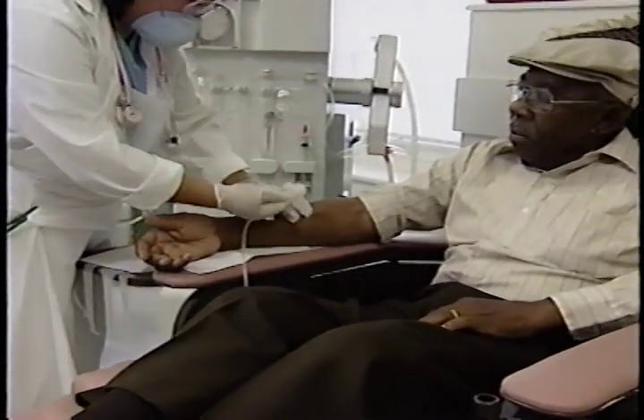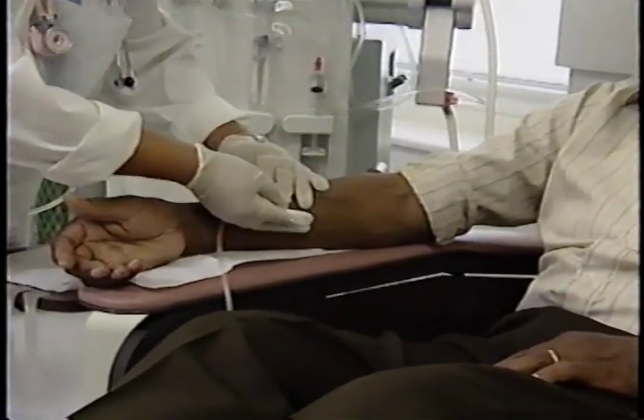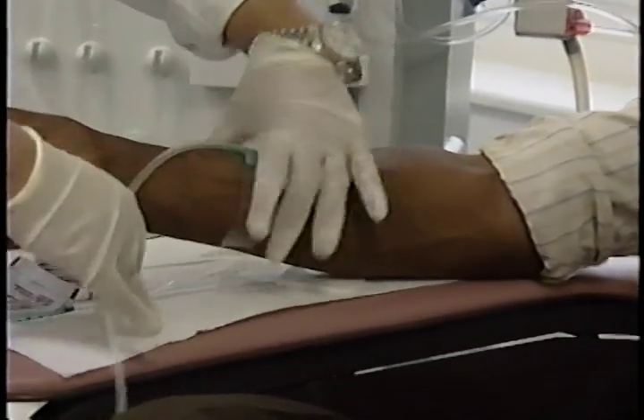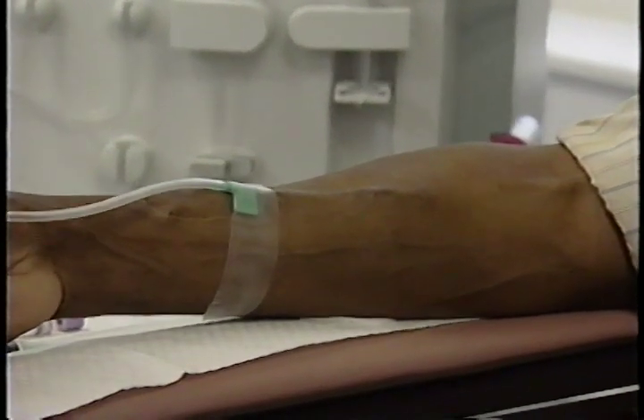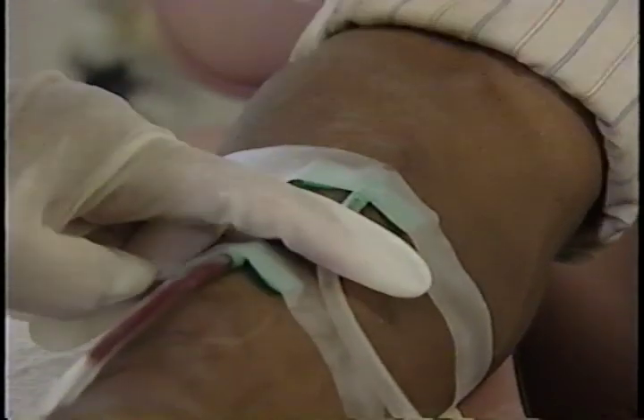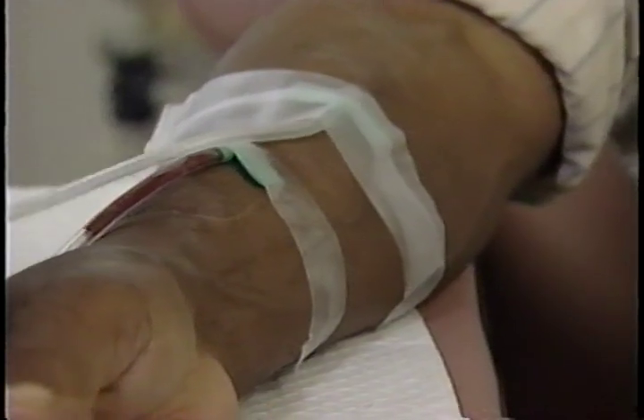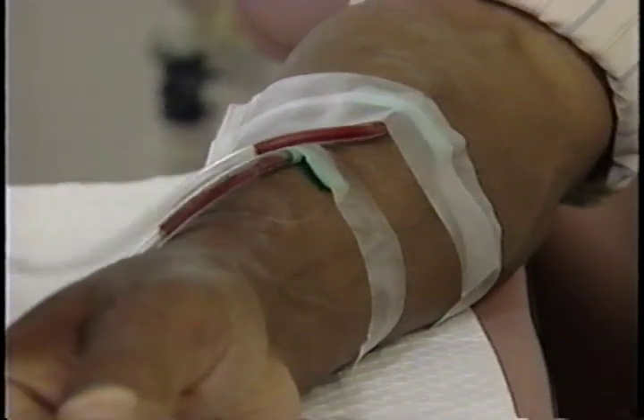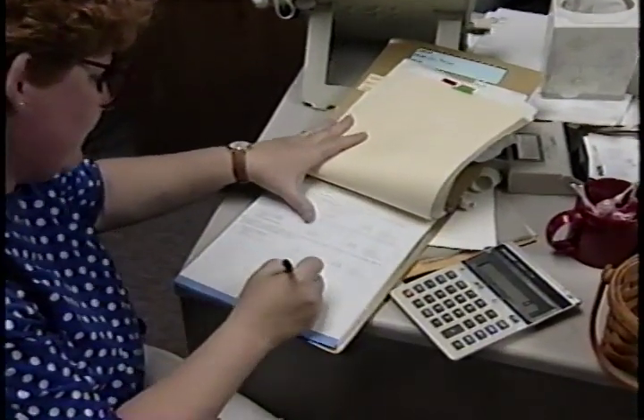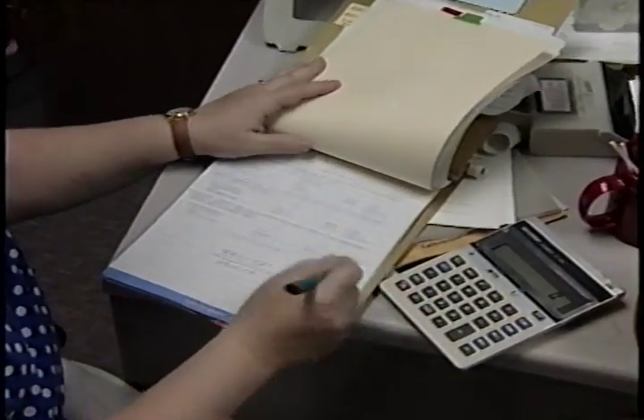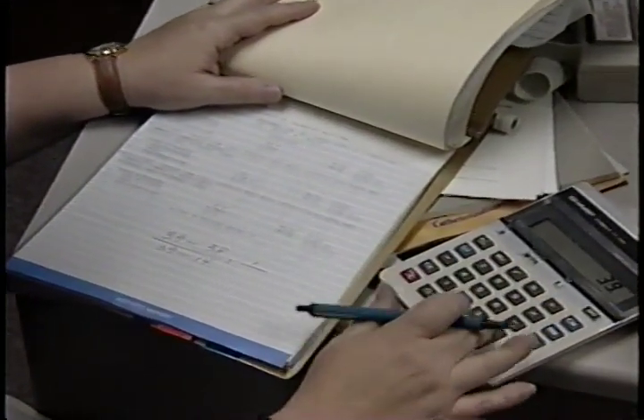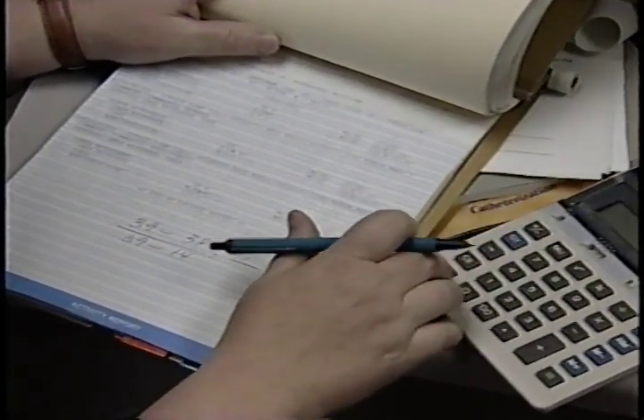Another frequent problem is recirculation of blood through the patient's access. Recirculation causes the effective clearances to be reduced. Recirculation may be caused by a partially occluded access or by improperly placed needles. This could include being placed too close together, pointing in the wrong direction, or actually reversing the arterial and venous connections. Recirculation studies should be performed to evaluate whether or not an access is failing. Some small amount of recirculation may be unavoidable and acceptable as long as the prescription takes this into account.